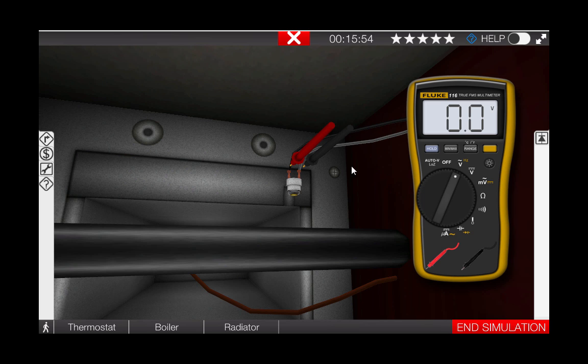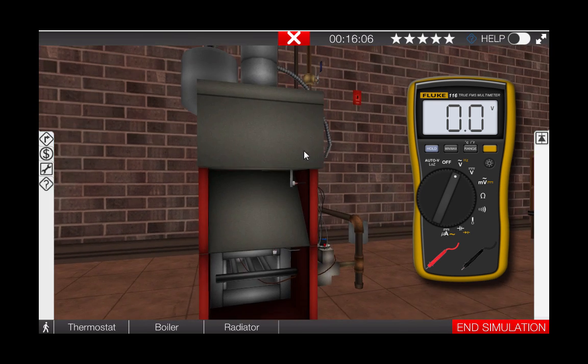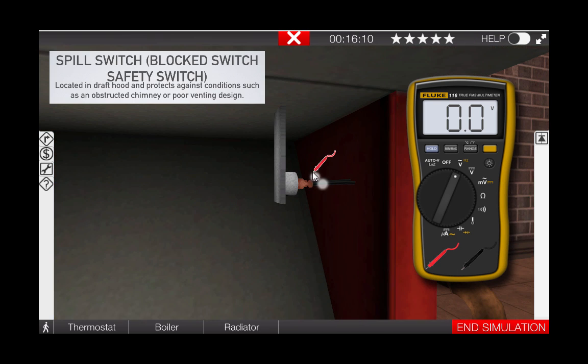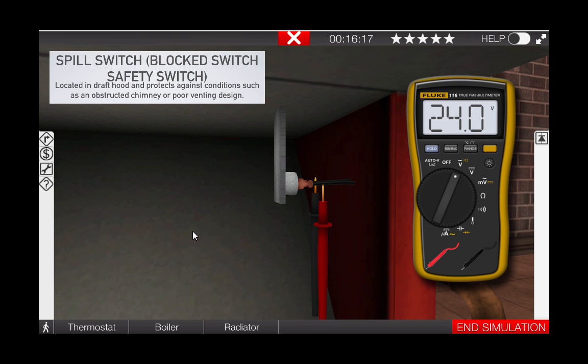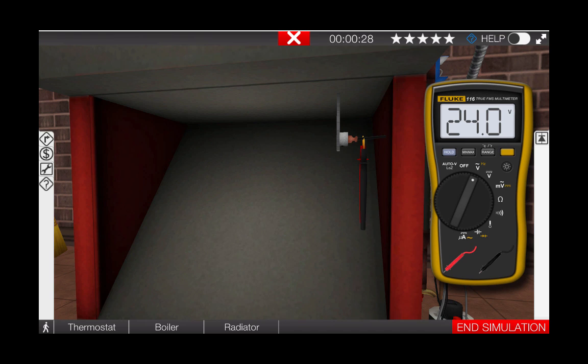Next, we're going to store the meter leads and proceed to the block vent safety switch, or spill switch. Zoom out and locate the spill switch up inside the draft diverter of the boiler. Zoom in and place the meter leads on the glowing hotspots at the spill switch. Here we can see 24 volts is measured across the block vent safety switch, indicating that the switch is open. Prior to replacing this switch, it is extremely important to inspect the flue and chimney for obstructions as well as proper vent design. A spill switch should never be just reset without verifying these conditions first. We can replace the block vent safety switch, but only after verifying proper vent design and that there are no obstructions in the flue or chimney.